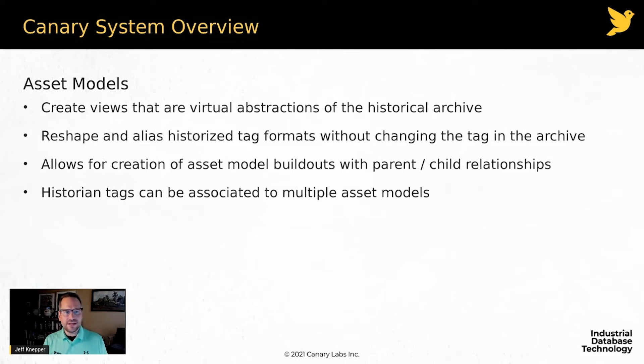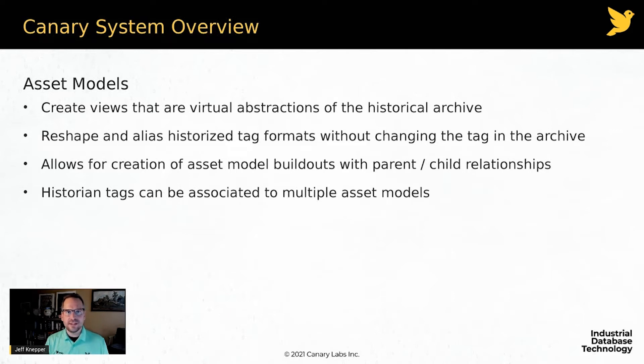I create virtual abstractions of the tags in the way they appear in the historian, and because they're virtual, I'm not replicating the data. This can be as simple as aliasing tag names. I might have tags being logged from a SCADA system, and naturally those tags will have the same names as my SCADA system.